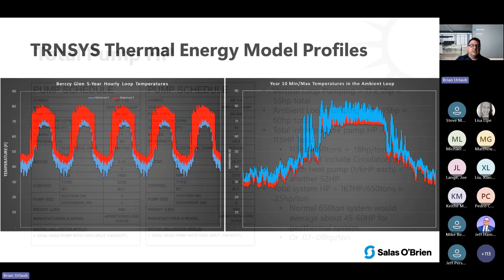All right. Now, the other thing I just want to touch on real quick about single pipes, because I hear a lot about pump energy. If you're going to compare this to a single building like a school, and you look at the ASHRAE handbook and you look at what Dr. Kavanaugh would consider low pump energy for a geothermal system, these systems would not qualify as an A or a B grade within that ASHRAE standard. But these are much different systems. Of course, you're going to have more pump energy here because you have a network that you're trying to serve, a whole bunch of buildings at once versus just one building and one loop field.